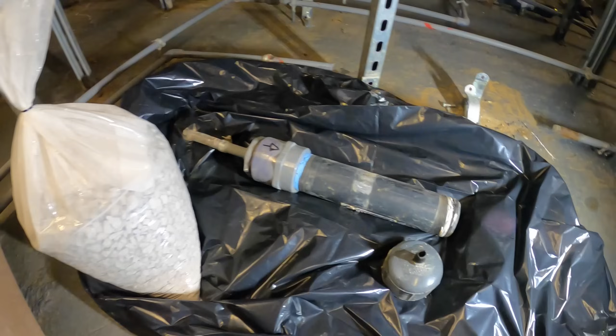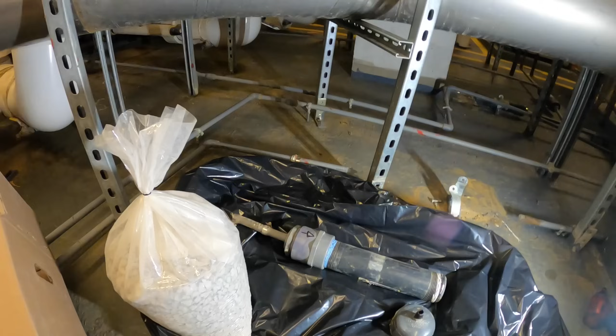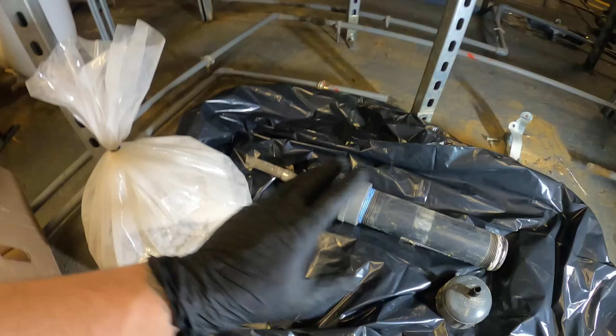Before I replace the media inside this filter, why are we doing this and what is a condensate neutralizer? These boilers are high efficiency boilers, and they produce acidic water in their condensate. Because of that, before it goes into the drain line system, you want to filter out all that acidity, otherwise you'll have problems. So basically it's just a filter for the condensate before it goes down the drain, before it seriously pollutes things.